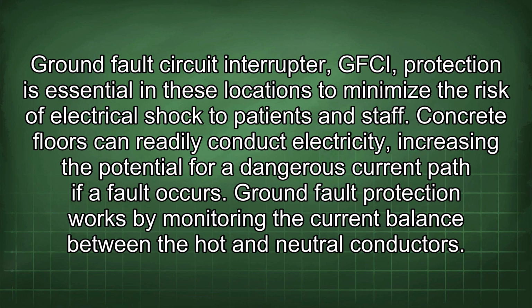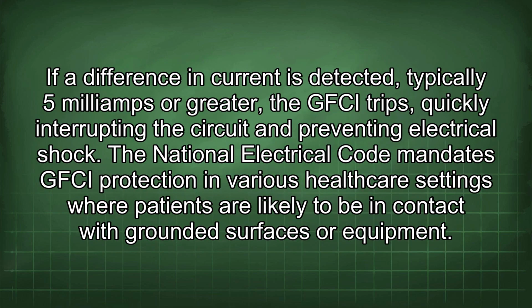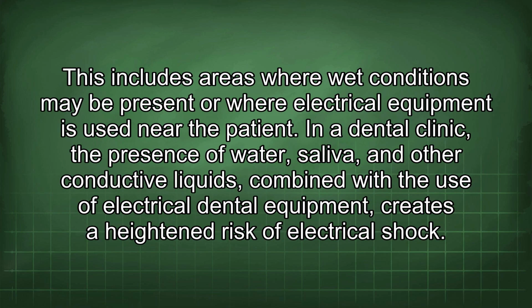Ground fault protection works by monitoring the current balance between the hot and neutral conductors. If a difference in current is detected, typically 5 mA or greater, the GFCI trips, quickly interrupting the circuits and preventing electrical shock. The National Electrical Code mandates GFCI protection in various healthcare settings where patients are likely to be in contact with grounded surfaces or equipment. This includes areas where wet conditions may be present or where electrical equipment is used near the patient.